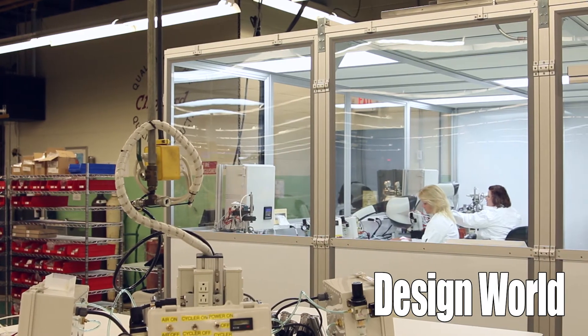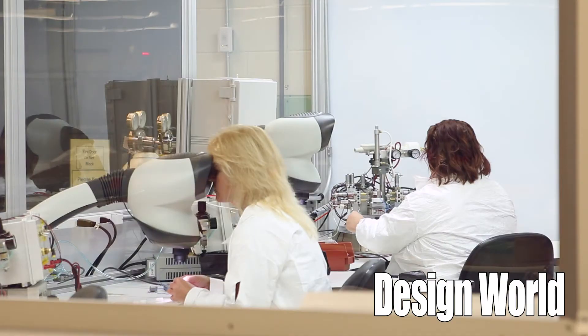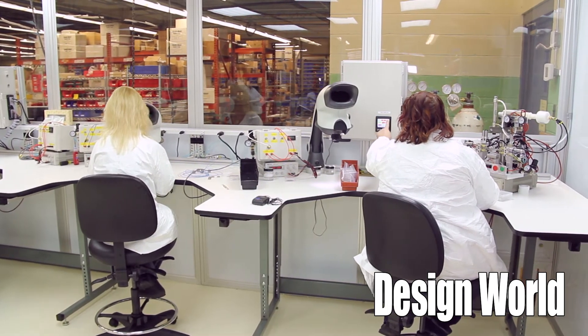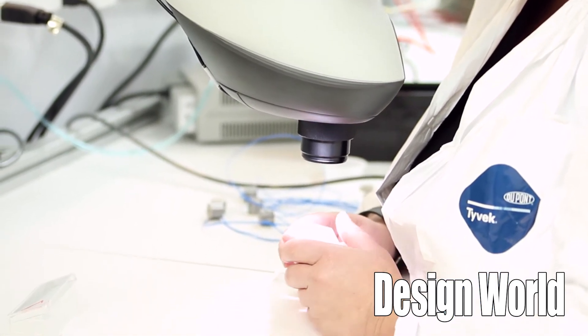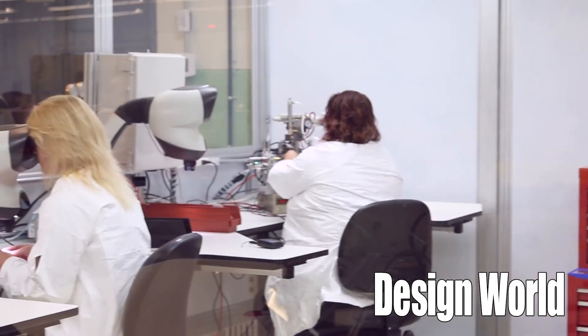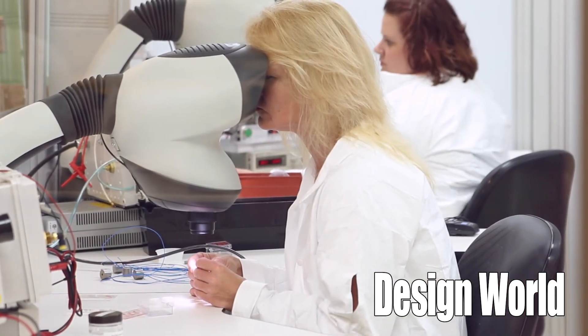Can you tell me a little bit about this room that we're in, Attila? This is a new facility here at Clippard for you guys, right? Absolutely. Right now we're currently inside a clean room that we assembled here at Clippard. One of the main reasons is for the cleanliness of the product line and to keep up with all of our manufacturing standards for this product line, for the medical instrumentation and diagnostic field. The clean room is humidity controlled, has HEPA filters, and all isolation valves are actually built in this room, assembled, and tested 100%.